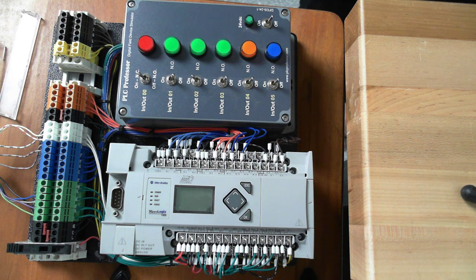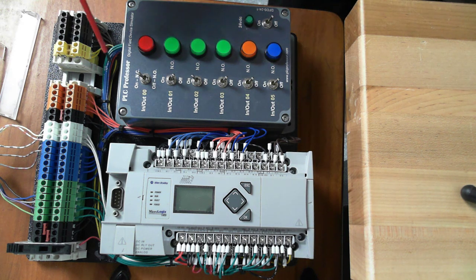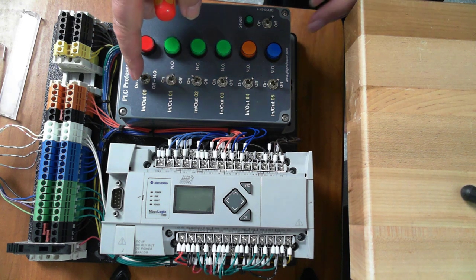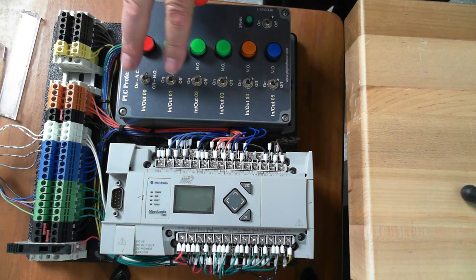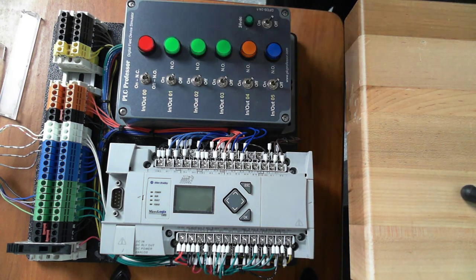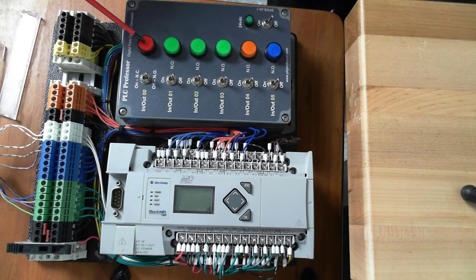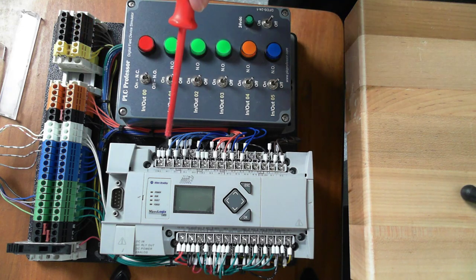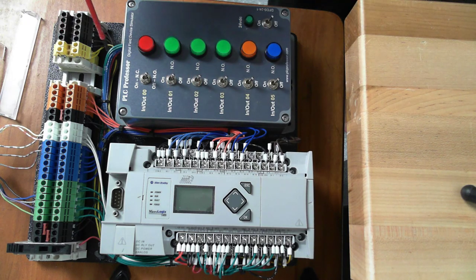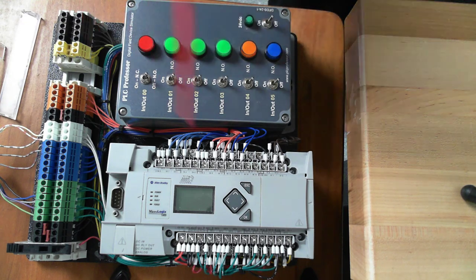So coming out of the top of this field device simulator, we have our green and blue wires, green for output, blue for input. We have a plus 24 volt red wire and a minus or 0 volt DC wire. Okay, and all of these inputs, or all these devices here, remember we have a toggle switch and a form C contact push button. They are wired in series and go through the blue wires over to the inputs 0 through 5. And then we also have green wires that come in and feed 24 volts DC to these LEDs from over on this side.